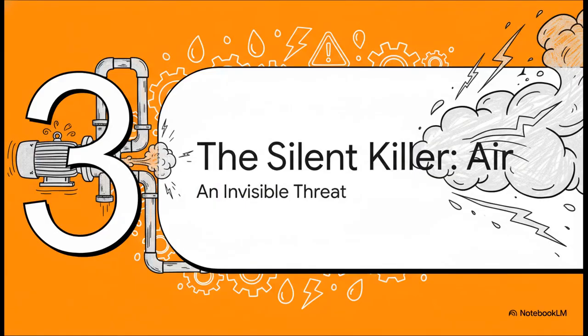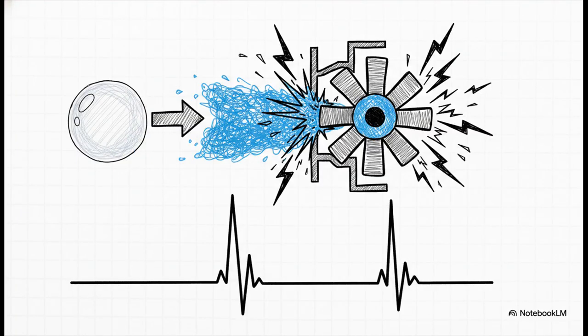Okay, so our pump is already overworked from the get-go. Now, let's introduce the first villain in our little drama. Air. It's the silent killer that can sneak into the system and cause, well, catastrophic damage. Here's the best way to think about it. When air gets into the suction line, the pump's impeller suddenly goes from pushing dense, heavy water to, basically, nothing. And then, a split second later, it slams back into water again. This creates these violent, irregular shock loads. It's literally like giving the system a mechanical heart arrhythmia.